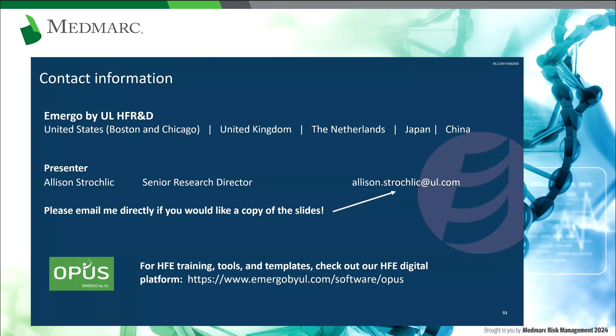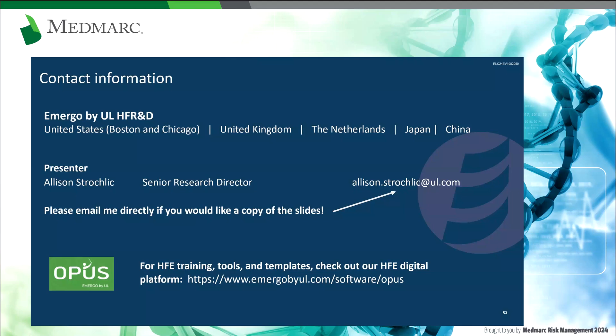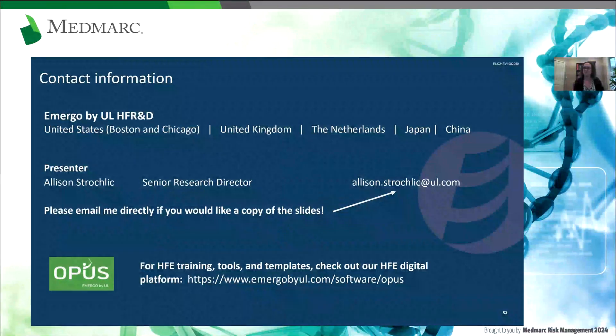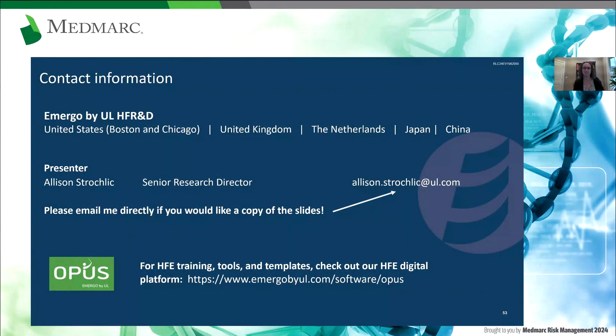One other question that came in is more of a best practices question: if a product seems very common sense and very straightforward to use, is it enough to videotape a demonstration to prove that you have tested the human factors? I'm not quite understanding what that means in terms of a video presentation. The FDA, at least, does expect that if you have critical tasks associated with use of your product where use could lead to some use-related risk, you need to conduct a validation test with representative end users and have people interact with the product.